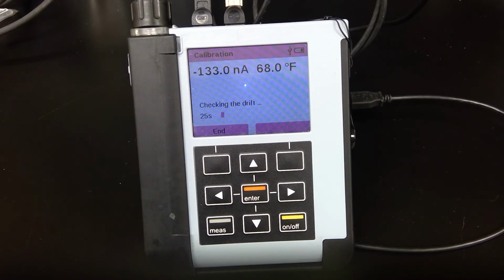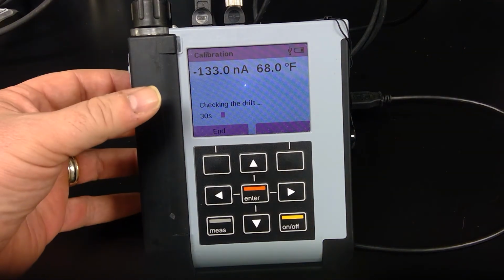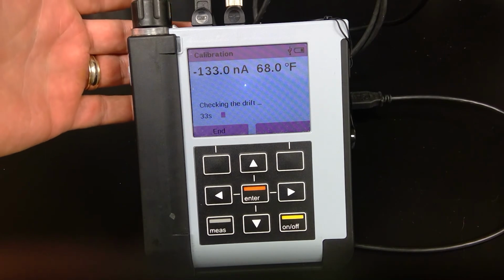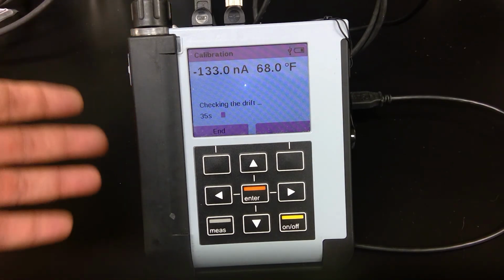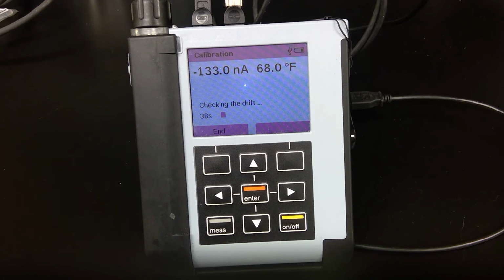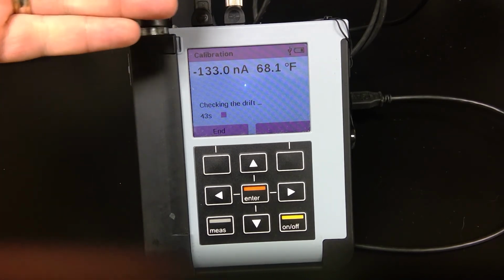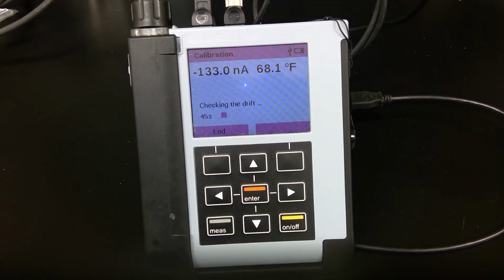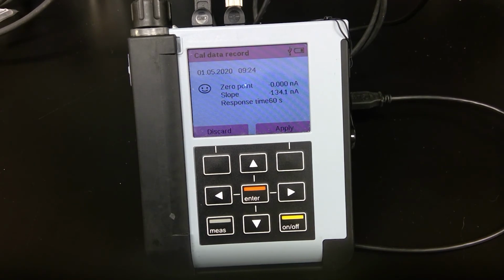Now, I recommend that once we get to the point where we have the final calibration results and we apply it to the sensor, you leave the DO probe connected to the Portavo, powered up, as you take it out to the field. That way, you want to try to minimize the amount of time that the sensor is not connected to a power source. Less than 5 minutes, you're okay. Once you go over 5 minutes being disconnected, you want to give it some time to polarize. And if you look in the box, there are instructions on how much time, based on time disconnected, it needs to be polarized to ensure that there's no drift.